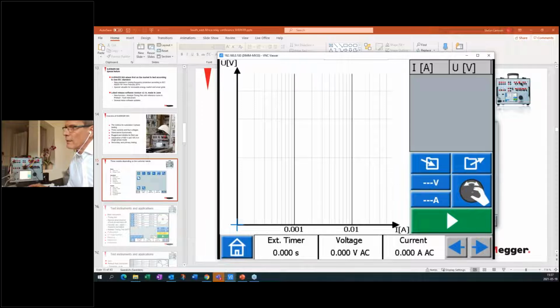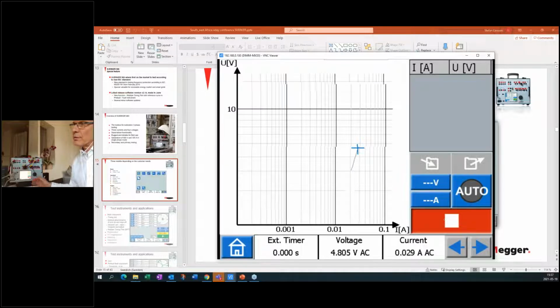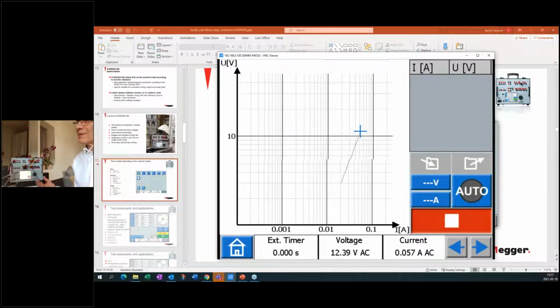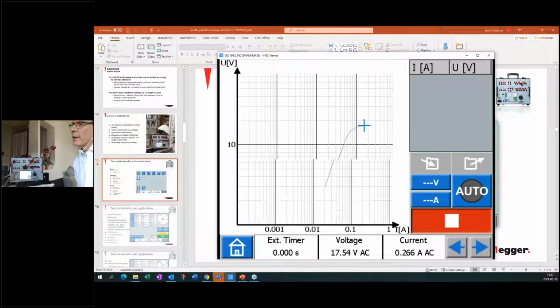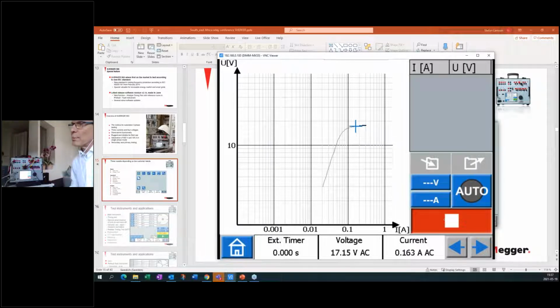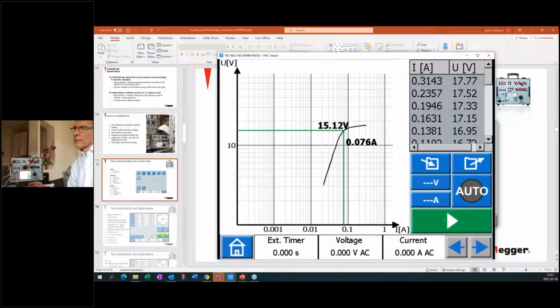Then I click here on the symbol, it says auto, and then I'm ready to go. So I press the play button, and then it starts to inject the voltage secondary in the current transformer, and it quickly calculates where the knee point is. When it's going back, it's doing a more detailed calculation to find the voltage knee point. Now it does the demagnetization of the current transformer, and then we will see, yes, now it's ready, and we get the result here.